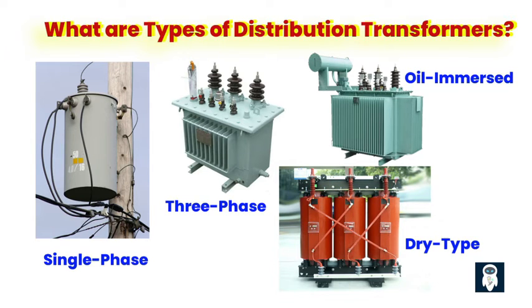Oil-immersed distribution transformers are filled with special insulating oil, which helps to dissipate the heat generated and provides extra insulation. They are designed to be safe and effective. In contrast, dry-type distribution transformers skip the oil and instead rely on solid insulation materials, such as epoxy resin, to keep things cool and prevent any mishaps. These transformers are favored in areas where fire safety is a top priority, like hospitals, schools, and shopping malls.